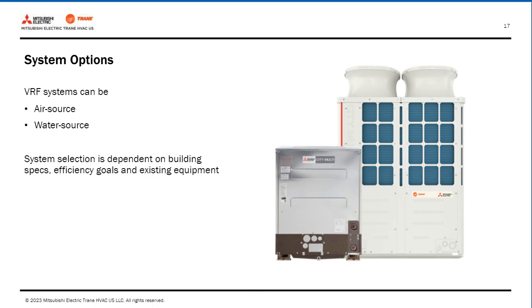The condenser on the right is the air-cooled version. It could be either mounted outdoors, or we have other instances where the air-cooled condensers are even mounted indoors. And then the one on the left there is the water source condenser. Those can be stacked, and that's what we've utilized for both the comfort cooling and also the outdoor air processing for the entire Credit Human building. So an air source system draws heat from the outdoor air to provide heating, and in cooling mode, the system rejects heat to the outdoor air. Water source systems operate similarly, but they draw heat from a nearby water source during heating and reject heat to the water source during cooling.